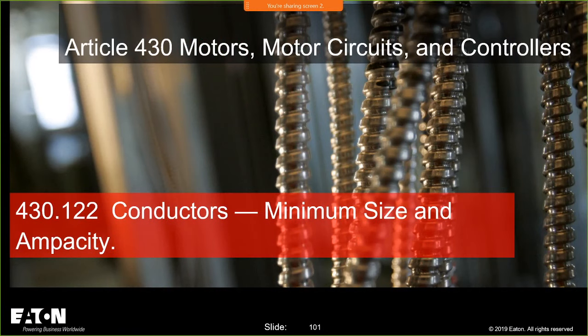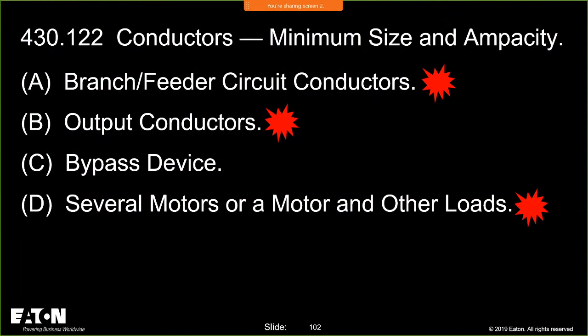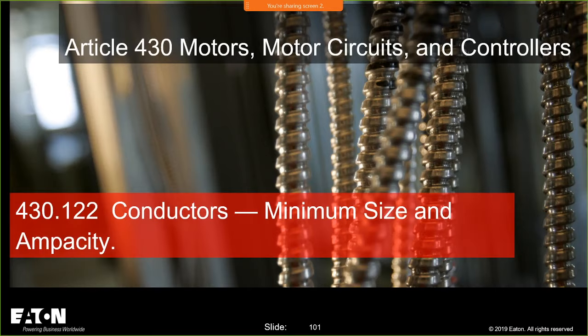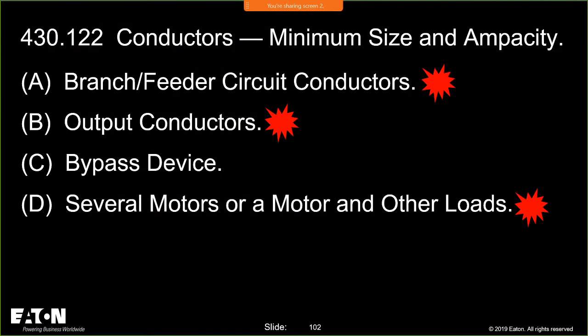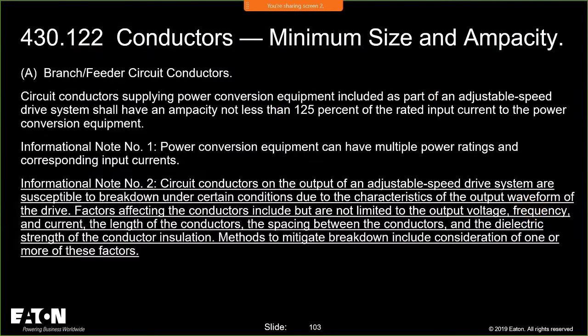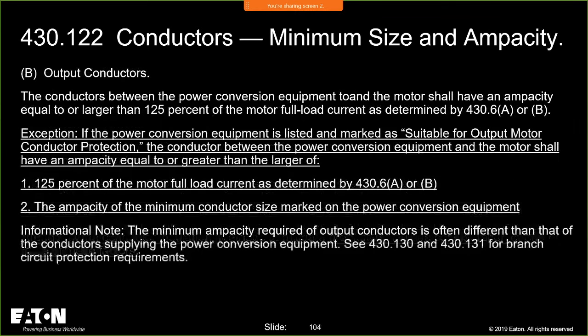And the last thing I want to cover, I believe this is the last thing, is the ampacity discussion I mentioned earlier. We did some cleanup on branch, feeder circuit conductors and output conductors. Circuit conductors on the output of an adjustable speed drive system are susceptible to breakdown under certain conditions due to the characteristics of the output waveform. So we have to consider those conditions, and we have to make sure that we protect those conductors in light of the inhospitable conditions that we are going to put them in.